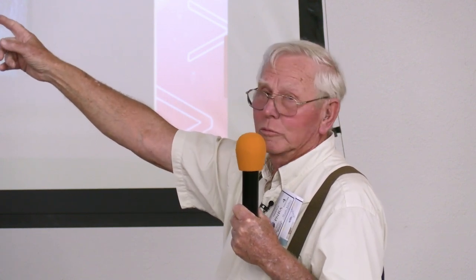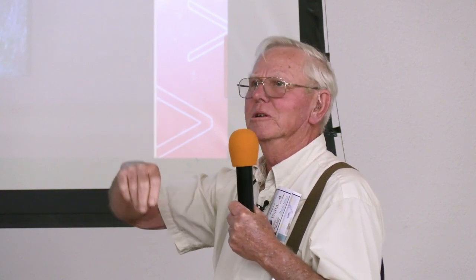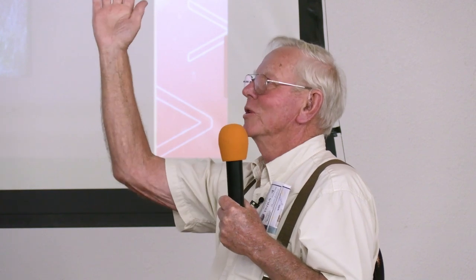The wind would come out of the southwest in the wintertime and wiggle that rack around. Then when you had to operate that switch, opening it wasn't too bad, you might draw an arc about a foot long, no big deal. Then you got the switch open like so, a big blade thing going up like this.